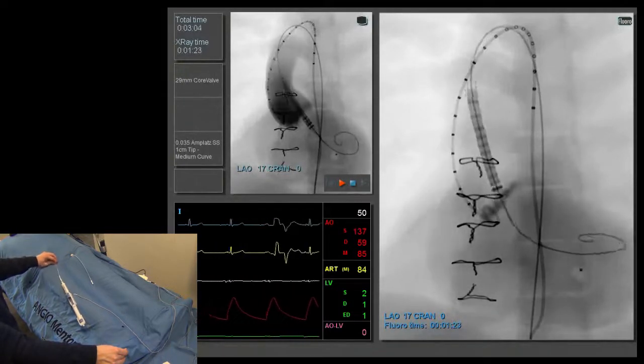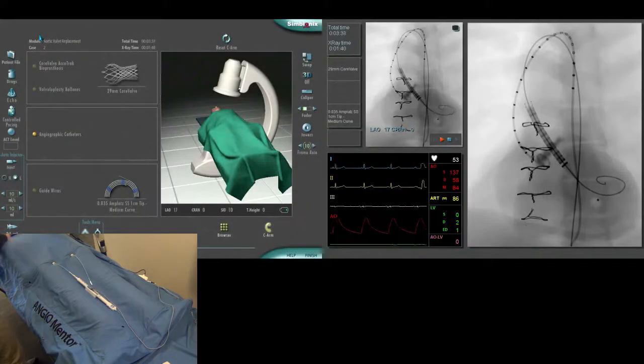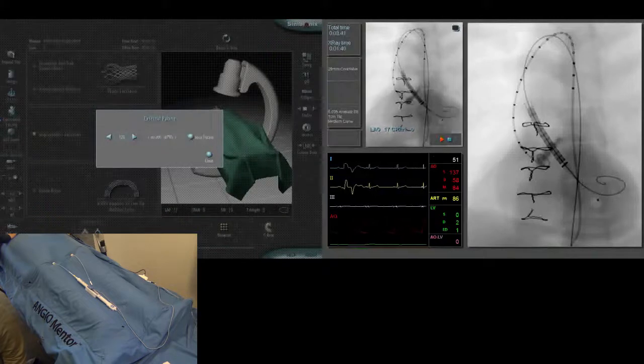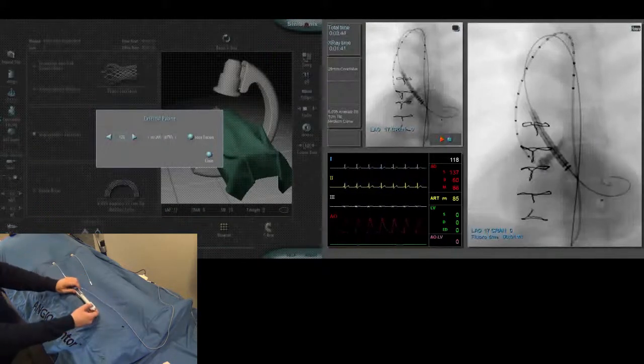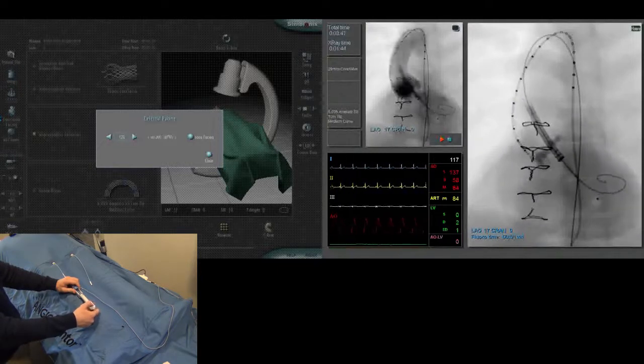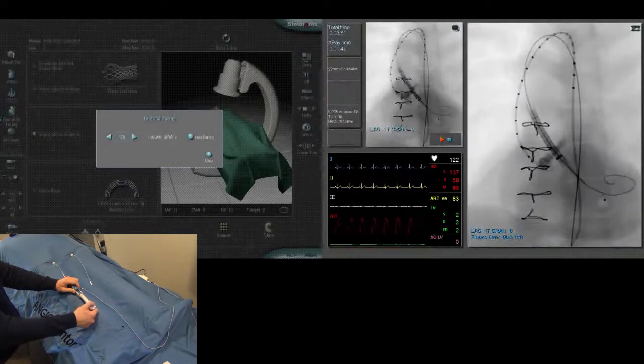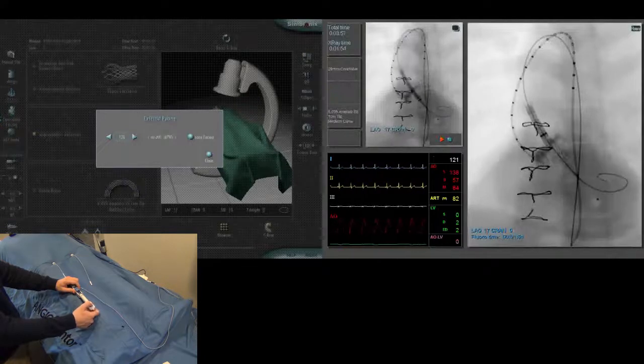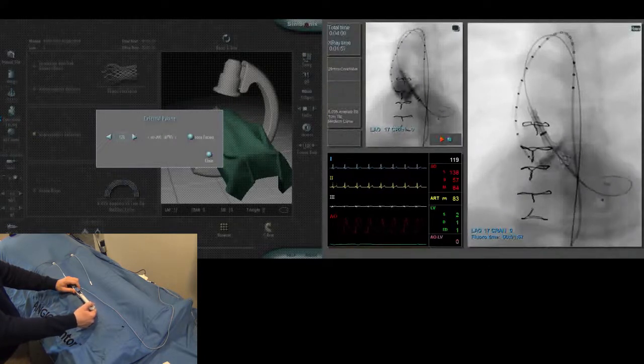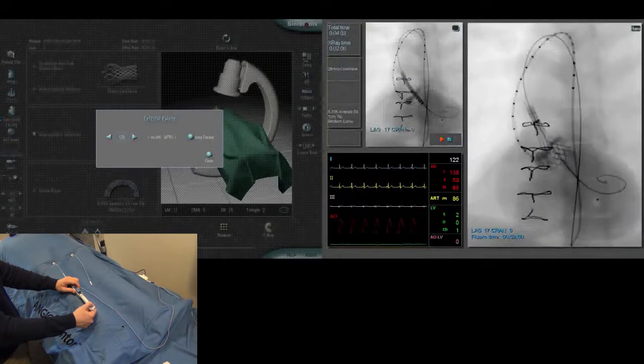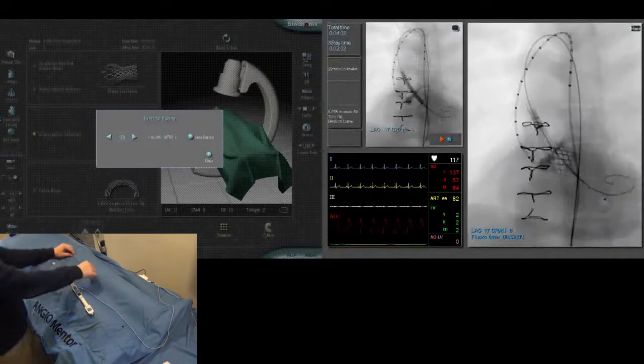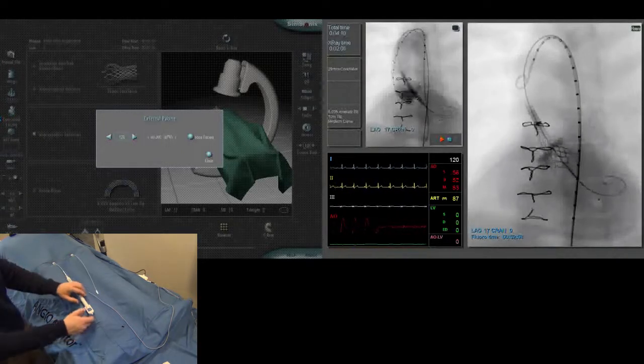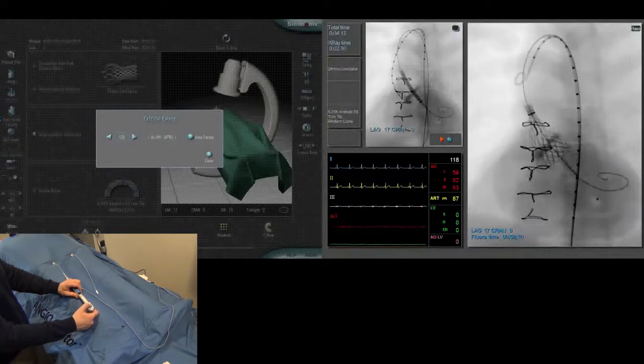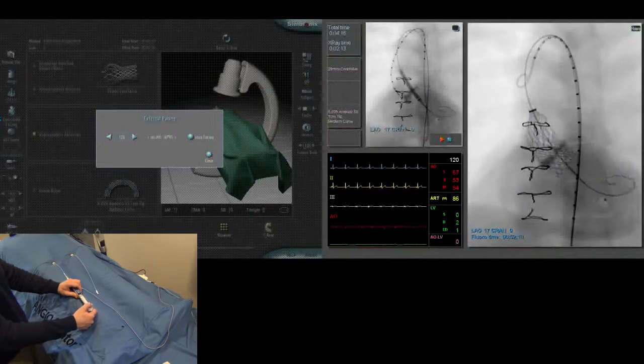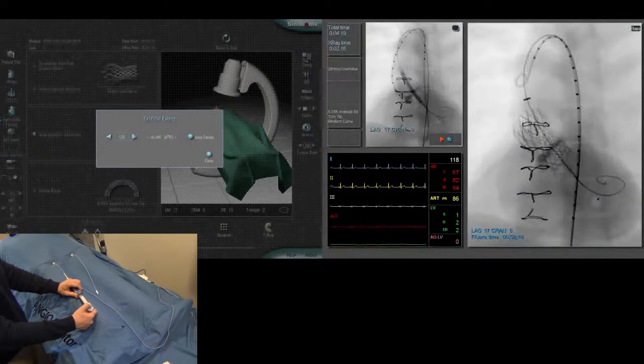And trying to control now, this is the beauty of this system, you can actually look for new ways to improve your accuracy. And the first step would always be to pace a little bit faster. It's not the rapid pacing of BAV, but rather a moderate, gentle pacing at 90 to 100, which allows for better stability. And as you can see here, now under pacing, slow deployment, step by step, and injection should be done here. And after injection, the pigtail is pulled out and release is nicely completed.